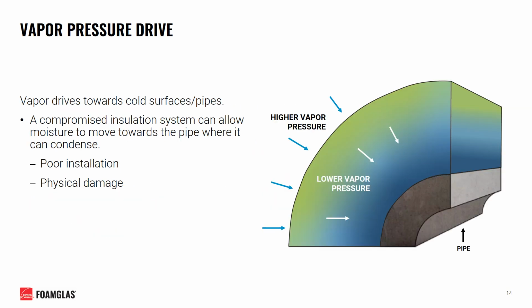One can view the topic of vapor pressure similar to that of normal pressure, and that is, vapor will always move from areas of high pressure to low pressure. Or you can think of it as moving from warm air to cold air, or in this case, towards a cold surface of a chilled water pipe. An insulation system with a compromised vapor barrier can allow this moisture in the air to move towards that cold pipe where it can then condense into liquid moisture. This insulation system can become compromised due to initial poor installation or damage that happens after the fact, whether that be from maintenance activities or typical pedestrian traffic that happens to be in the area.